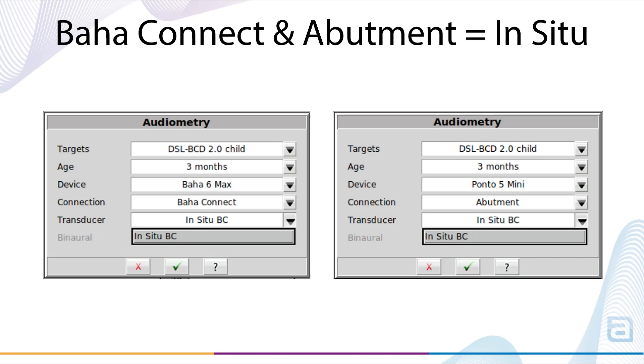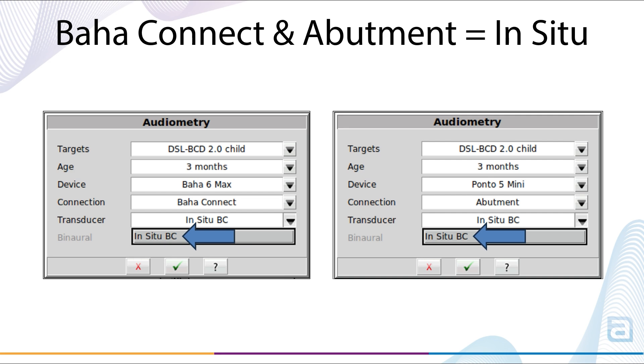Please note that Baha Connect is Cochlear's proprietary name for their abutment connection, where Oticon Medical uses the generic term abutment. Both Baha Connect and abutment require in-situ dial-level hearing thresholds for DSL-BCD 2.0 prescriptive target generation. As such, only the in-situ-BC transducer is available when Baha Connect or abutment is selected.